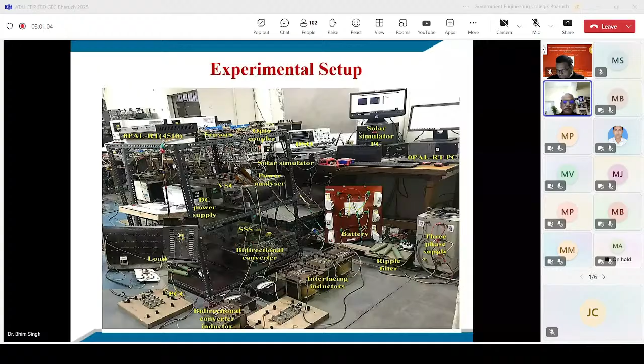And when the grid has appeared, here is the resynchronization of the grid. You can see the grid came here, and after 5-6 cycles we are able to synchronize with the grid and current starts flowing into the grid. But you have to estimate the angle on both sides—the grid side as well as the inverter side, or your local microgrid side—only then can you synchronize.